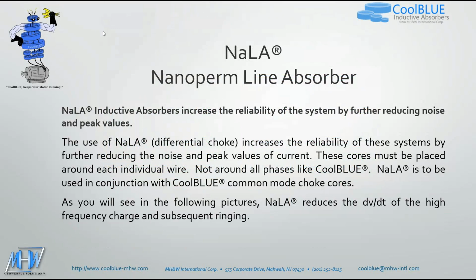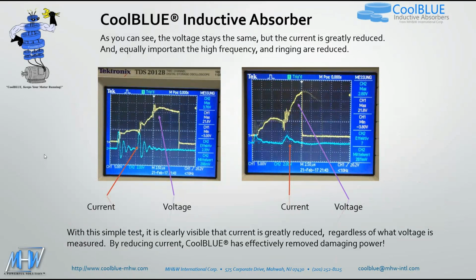What kind of currents are you looking to get below? Typically, based upon the bearing size that's in a motor, there are maximum current limits that those bearings can handle before they start to deteriorate. We have charts that show, for every bearing size, what those current levels should be below. So it's not just one number. It's all going to depend upon what bearing is actually in the motor. Could you send me those charts? Yes, we can provide that through Lynn at DREISILKER. Okay.